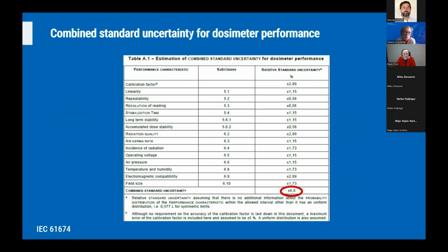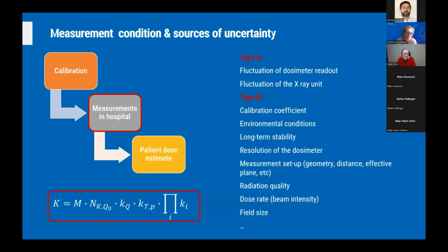This standard also provides an example of combined standard uncertainty for the dosimeter performance of a multimeter, and it's quite useful because it identifies possible performance characteristics that might affect the uncertainty of measurements. In this example of a hypothetical dosimeter, the combined standard uncertainty of clinical dosimetry measurements is approximately 6.6%.